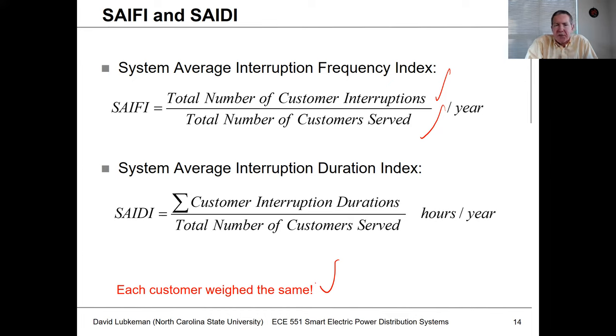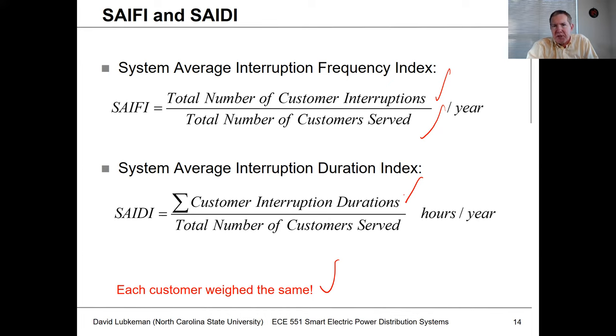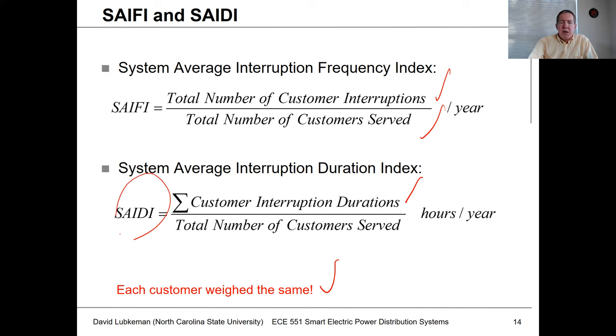The key numbers we'll use are SAIFI and SAIDI. SAIFI is the number of interruptions you're going to have per year — you take the total number of customer interruptions and divide by the total number of customers served, weighting every customer the same regardless of size. SAIDI is the number of hours or minutes you're out per year — if you sum up all customer interruption durations for sustained interruptions (typically longer than five minutes) and normalize by the number of customers served, you get the SAIDI number.